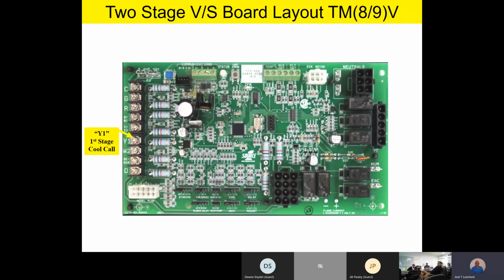And by the way, maybe make a little mental note of this. We have a product called a TH16, which is a 5-stage 16 SEER product that's perfectly compatible with this board. As a matter of fact, this board is extremely versatile. This furnace is very, very versatile. You can literally hook this thing up with anything in our inventory as far as single stage, two-stage, or what have you. Very, very versatile product. W2 is our second stage heating call. And again, team, we're going to recommend that if you have a two-stage furnace, always plan on a two-stage heating thermostat for the ultimate comfort and control.